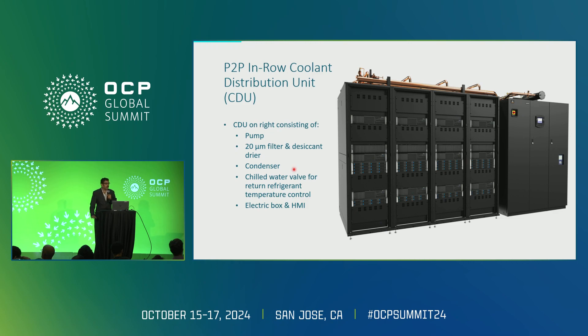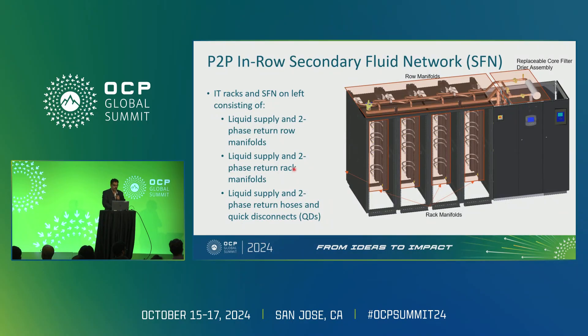Four racks of next-generation AI loads — one can put 200 kW in one rack now. We wanted to showcase the technology with loads going from zero all the way to full TDP, mix and match, 40 loops in parallel, with no temperature swings at all. Using some techniques from the HVAC industry — like a bypass valve — and working with the single-phase side, if we maintain 40 PSID pressure drop between inlet and outlet, you can plug and play any servers in the same system as long as the TDP does not exceed the CDU capability.